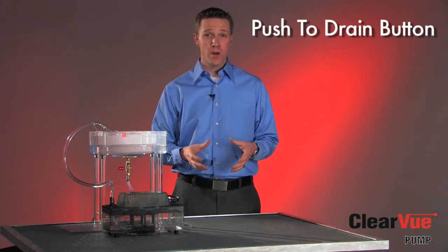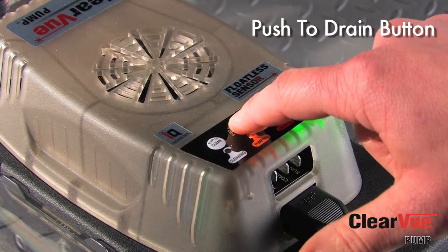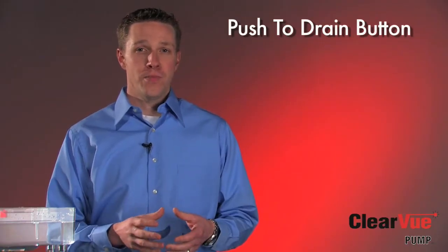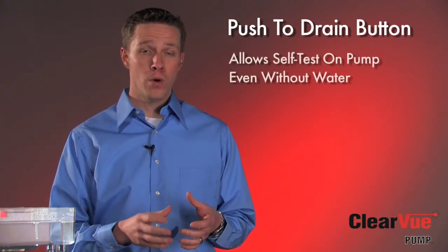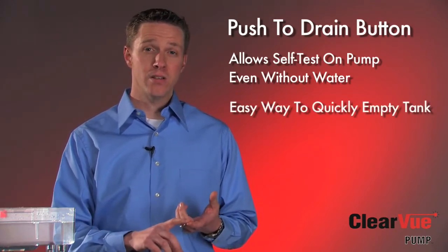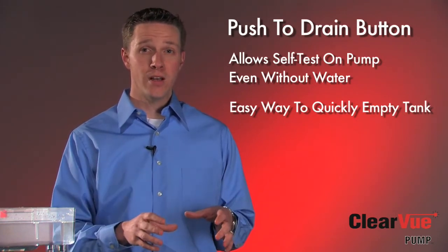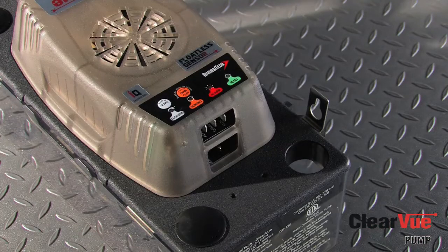The other feature I want to show you is our push-to-drain button. When there's water in the tank, you can simply push the drain button and ClearVue will quickly remove the water from the tank. With the push-to-drain button, there are two key features. The first is that the contractor can actually test the pump without having to pour any water into the tank. The second is that if there's been any cleaning to the air conditioning system or the pump itself that has any chemical solution in the tank, you can simply push that drain button and it will pump all that solution out without having to reach in to activate a float or shake the tank in order to get it to drain.